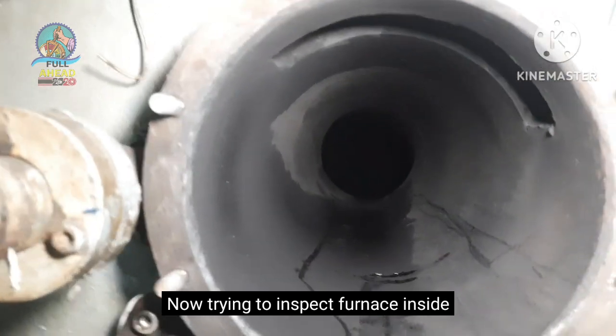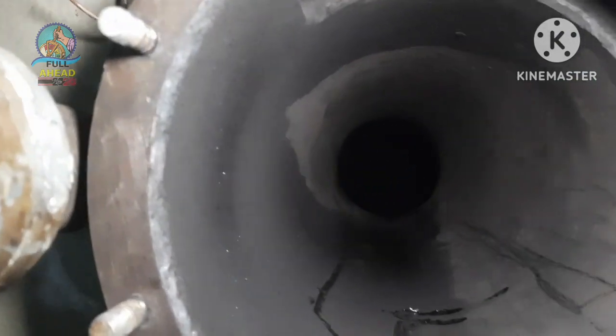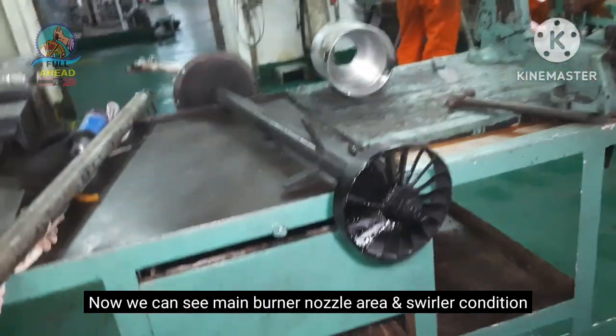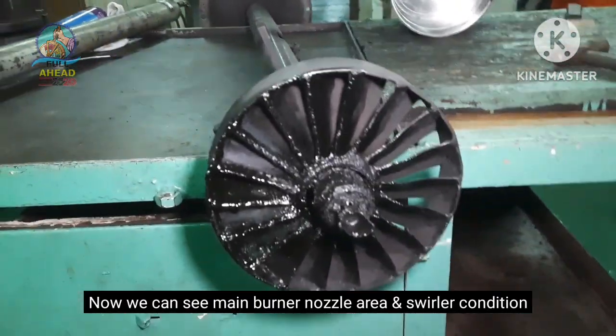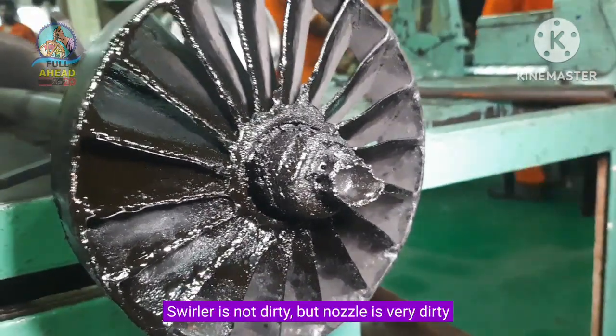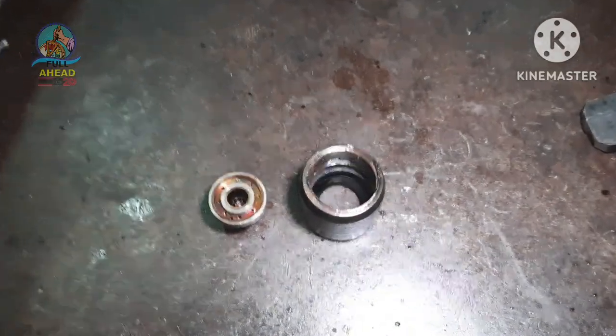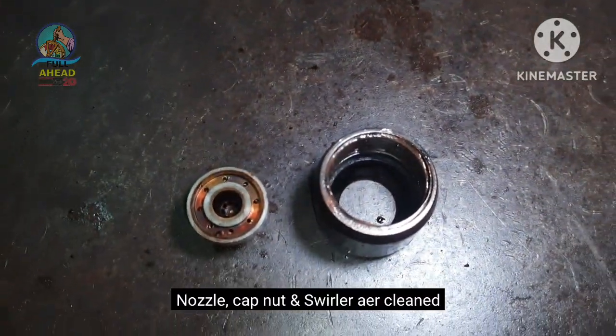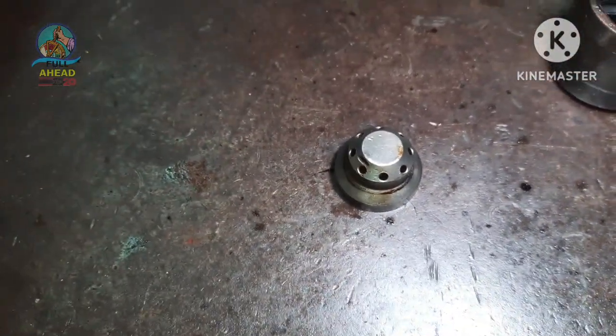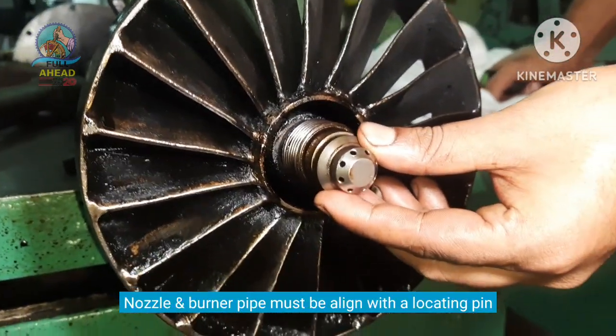For main burner opening, I will inspect the furnace. This is the burner of the furnace. If the furnace is dirty — the nozzle is very dirty. The main burner nozzle, cap nut, and swirler are cleaned. Now we can see the fitting of the main burner. The main burner supply pipe and the nozzle have alignment.